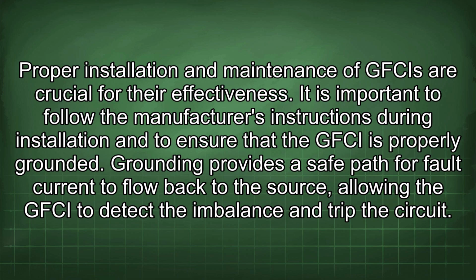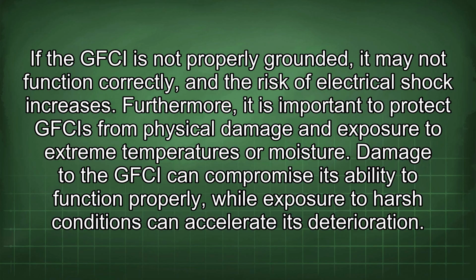Grounding provides a safe path for fault current to flow back to the source, allowing the GFCI to detect the imbalance and trip the circuit. If the GFCI is not properly grounded, it may not function correctly, and the risk of electrical shock increases. Furthermore, it is important to protect GFCIs from physical damage and exposure to extreme temperatures or moisture. Damage to the GFCI can compromise its ability to function properly, while exposure to harsh conditions can accelerate its deterioration.